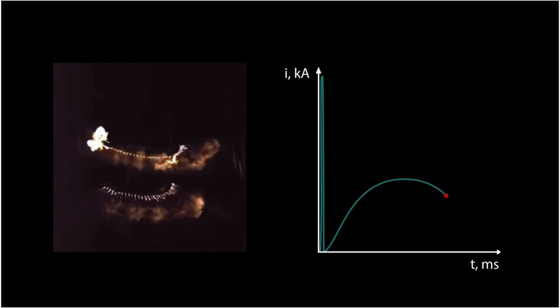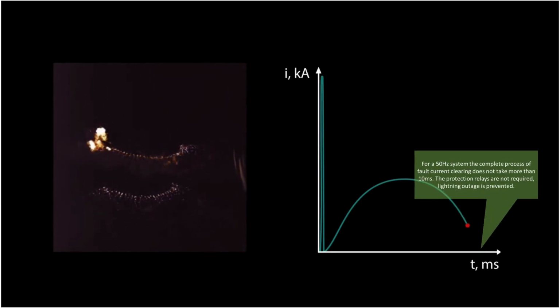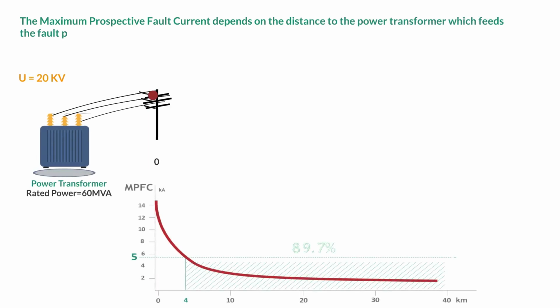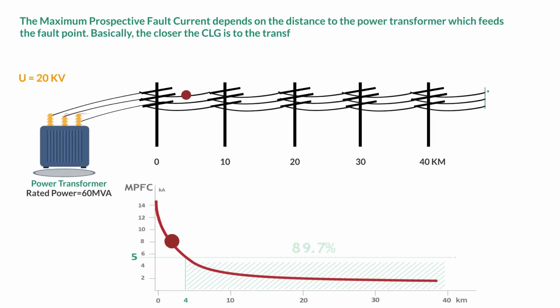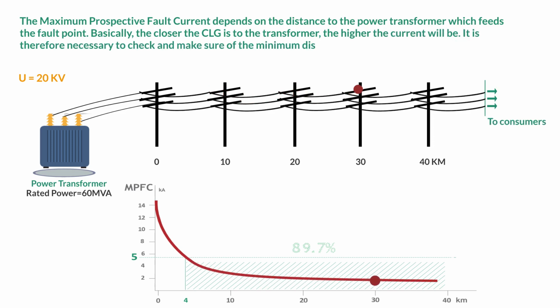Therefore, the CLG can be used for systems or locations where the prospective fault current is lower than the interrupting capability. The maximum prospective fault current depends on the distance to the power transformer, which feeds the fault point. Basically, the closer the CLG is to the transformer, the higher the current will be. It is therefore necessary to check and make sure of the minimum distance.